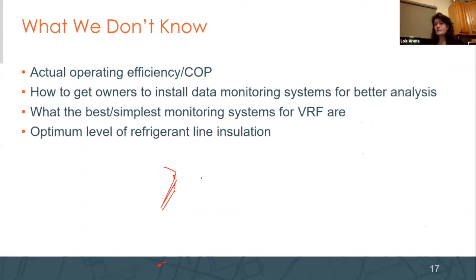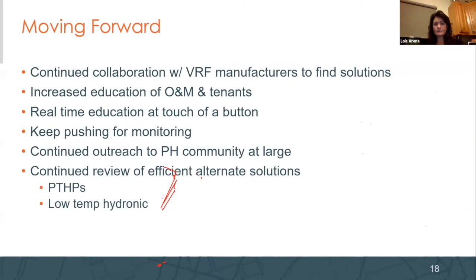And I ask you that because in our recent passive house project, where I've been evaluating the temperatures in a very painstaking manual way, the hallways and common areas are all overheating, the hallways in particular. I think that's because the refrigerant lines run down them and the domestic hot water recirc lines run down them. I don't know which is to blame, but they're 8, 9, 10 degrees over their set points, and the apartments are not. So it has something to do with the line sets that are running down the center. So moving forward, this is what I mean.